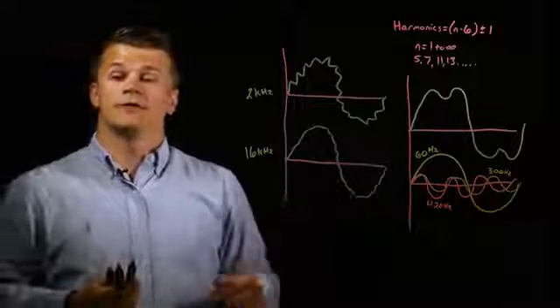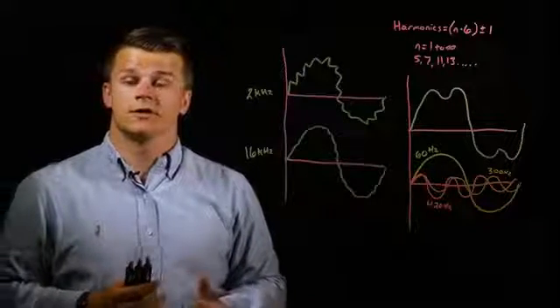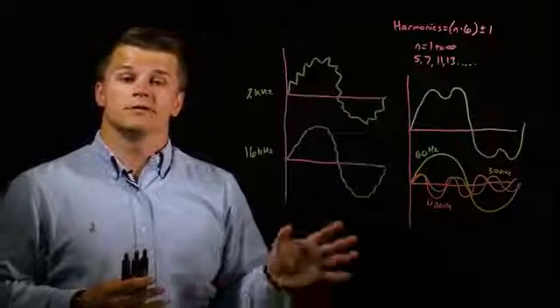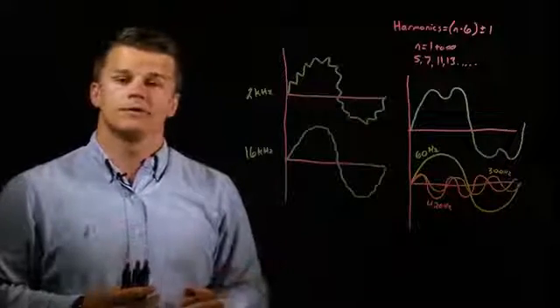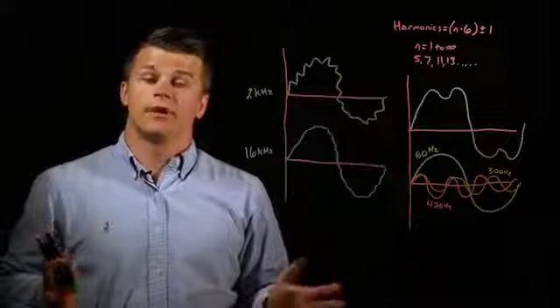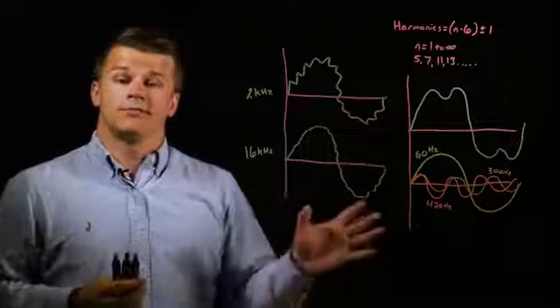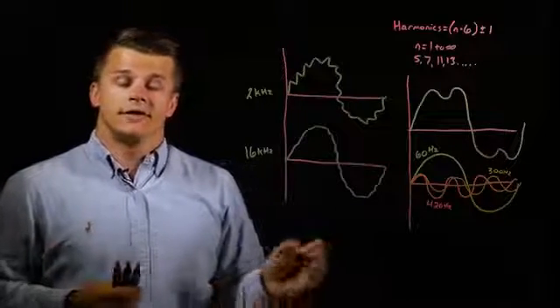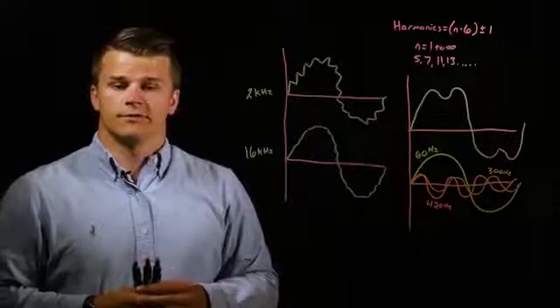And then this effect is more pronounced as the output frequency to the motor increases. So typically at KEB, we recommend your switching frequency is at least 10 times that of your output frequency. So for example, if you have a 400 hertz output, you'd want to have at least 4 kilohertz on your switching frequency. And if you have an 800 hertz output, you'd want to have at least 8 kilohertz on your switching frequency.